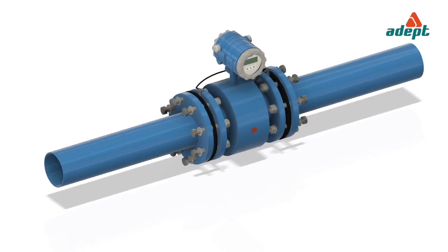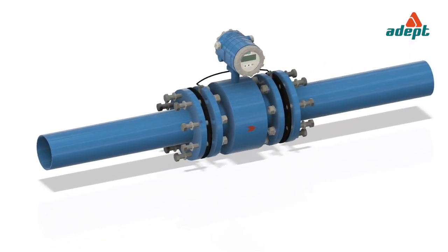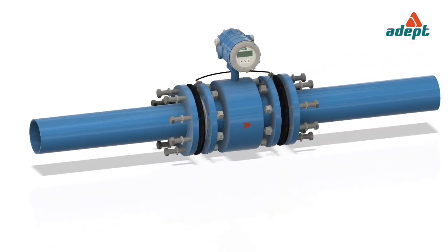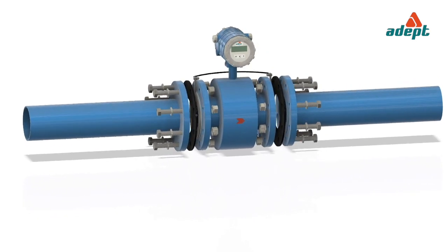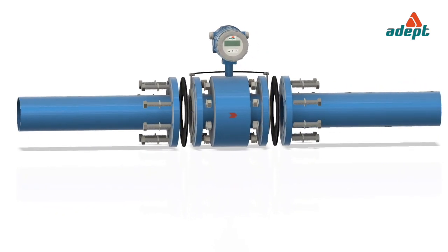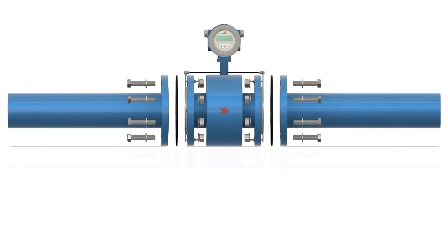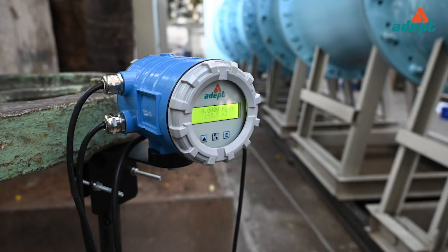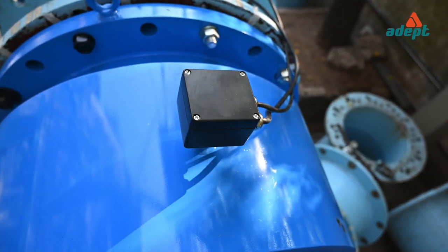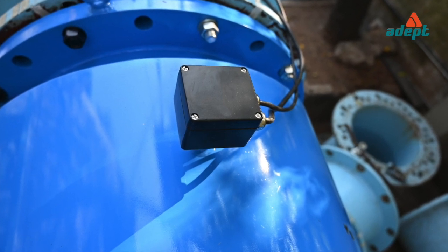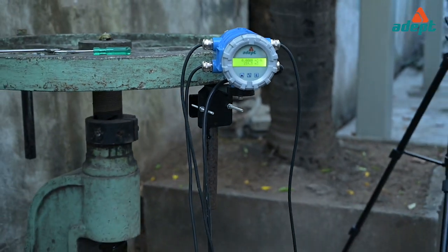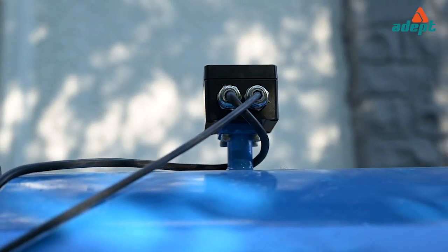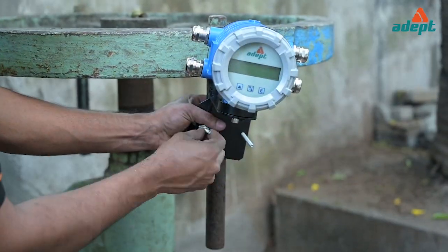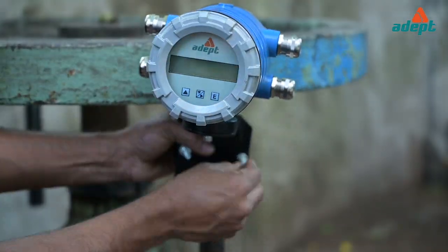In the case of an integral type flow meter, the transmitter comes pre-mounted atop the flow tube and therefore gets physically installed along with the flow tube. In the case of a remote type flow meter, a junction box comes pre-mounted atop the flow tube. The coil and electrodes cable is delivered connected to the junction box. The transmitter along with its mounting bracket is delivered separately.